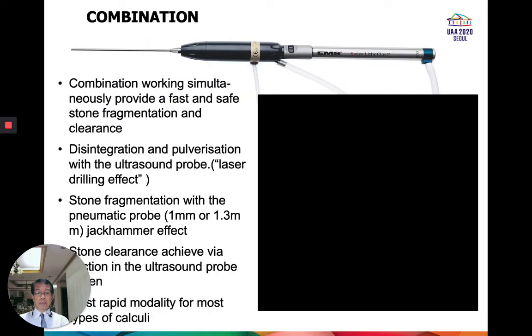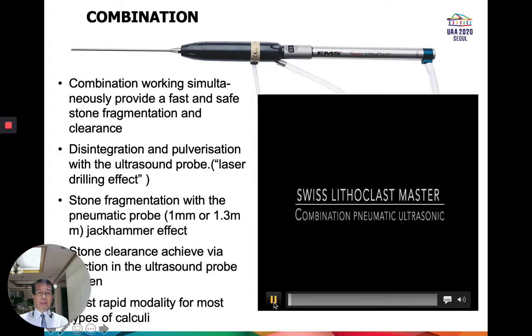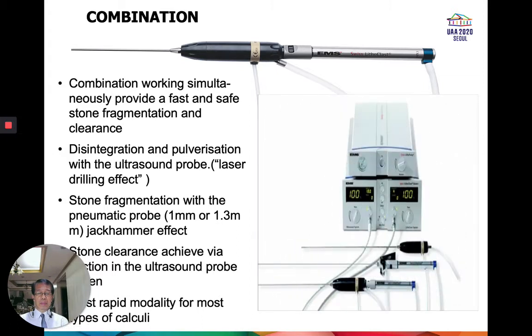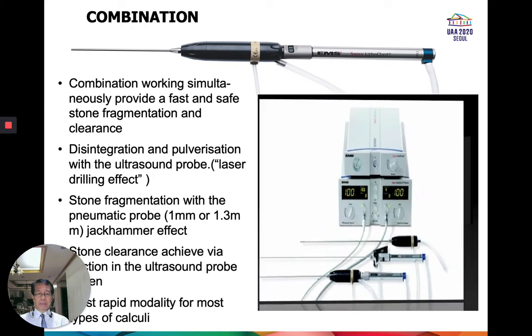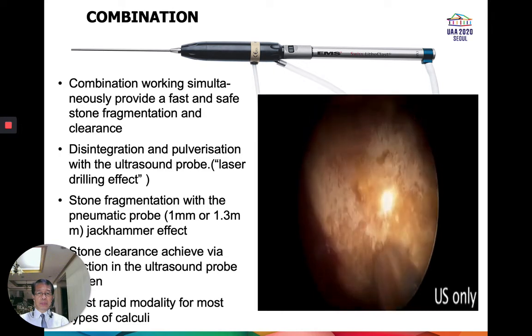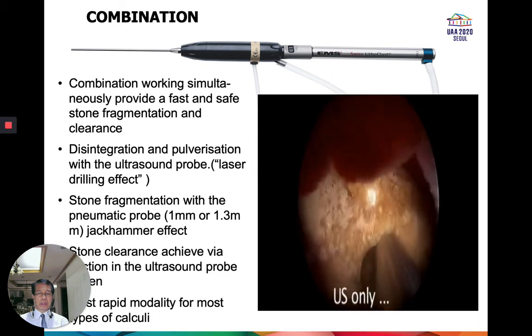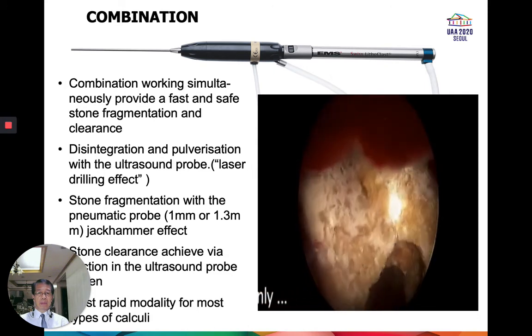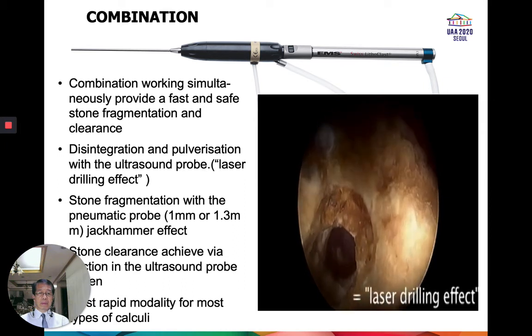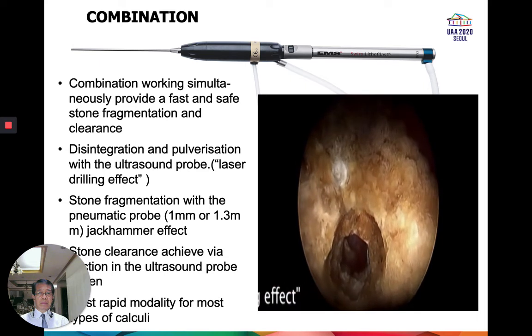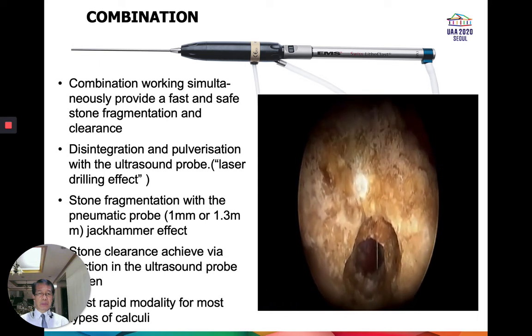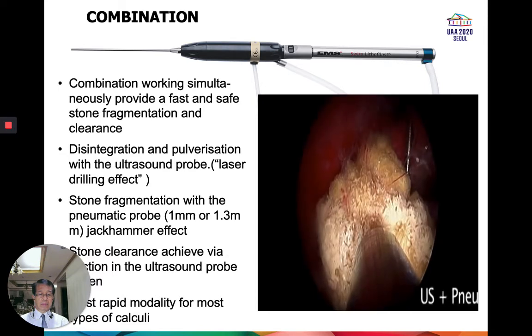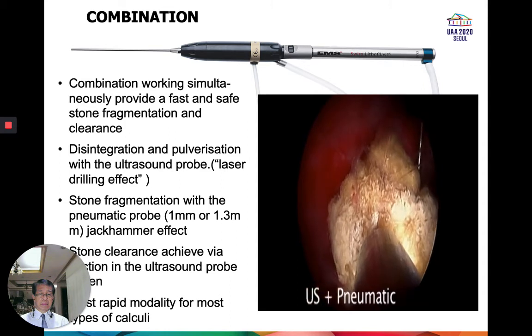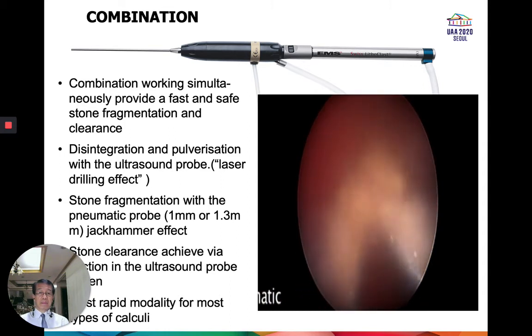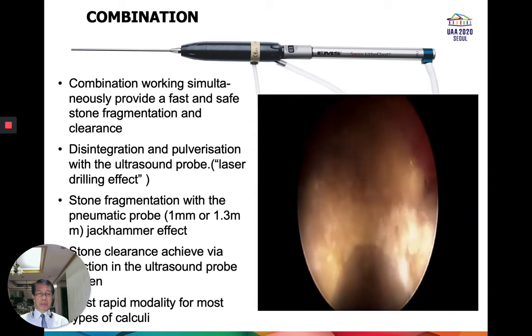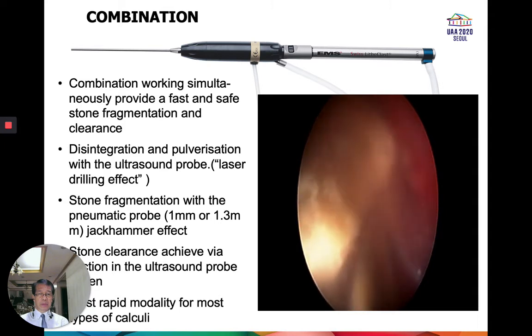The combination of both the pneumatic and the ultrasonic can efficiently fragment large and hard calculi. As shown in this slide, the ultrasonic will create what we call a laser-like drilling effect, while the pneumatic will fragment and disintegrate the stone through the jackhammer effect. Evacuation is finally accomplished through the hollow probe of the ultrasonic system connected to the suction device.